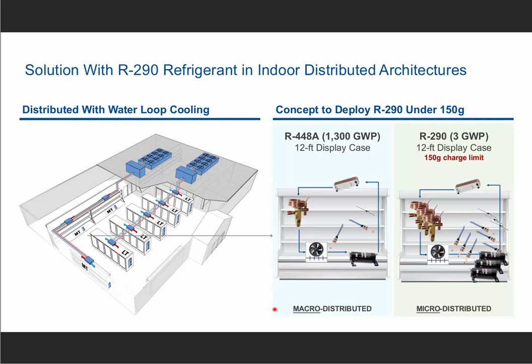cooled condensing units, before I had one unit basically providing the cooling load for the display case. So using as an example a 12-foot long display case with R-448 with propane, in order to keep those charged up to 150 grams in each of the circuits, some OEMs have been deploying three circuits in a single case. So basically, that's what we classify as the micro distributed architecture. So putting all the components that you have in the refrigeration circuit three times in that same case, so that you can keep the charges of propane up to 150 grams.